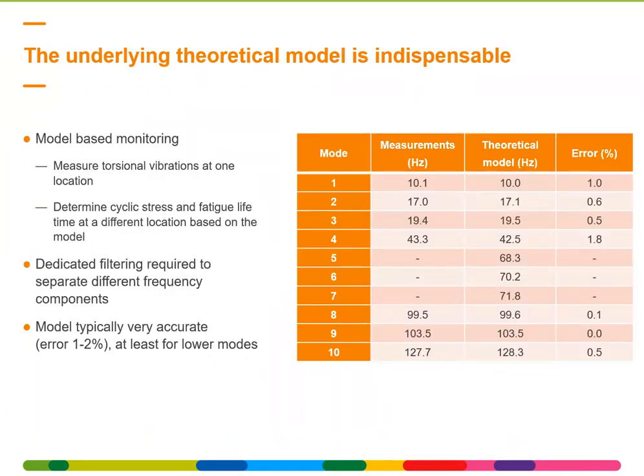So to summarize, the underlying theoretical model is indispensable. This is really important. It's a model-based monitoring. You do not monitor at the most critical location, but you measure at one location and you determine the cyclic stress and fatigue lifetime at a different location. You need dedicated filtering to separate the different frequency components, and the model typically is very accurate. So the error is in the 1 to 2 percent range. This is really very, very good, at least for the lower modes. An example is shown in the table on the right, where you can see for a steam turbine shaft line the error is lower than 2% for nearly all modes here. So that's the advantage of torsional vibrations. The model is not that complicated, and you can reach quite good accuracy. And so the correlation between the measurements and the assessment is quite well done.